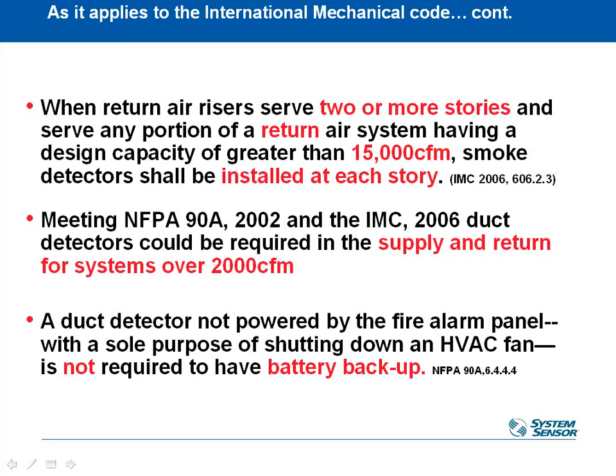So that's 15,000 CFM, just like NFPA. So that requirement is the same every floor. If you have a community that's requiring you to follow NFPA and IMC both, then yes, you do have to put detectors in both the supply and the return duct systems if it's above 2,000 CFM rooftop or air handler. So we got some products here we'll talk to you about in a little bit that are going to help you do that quite easily.